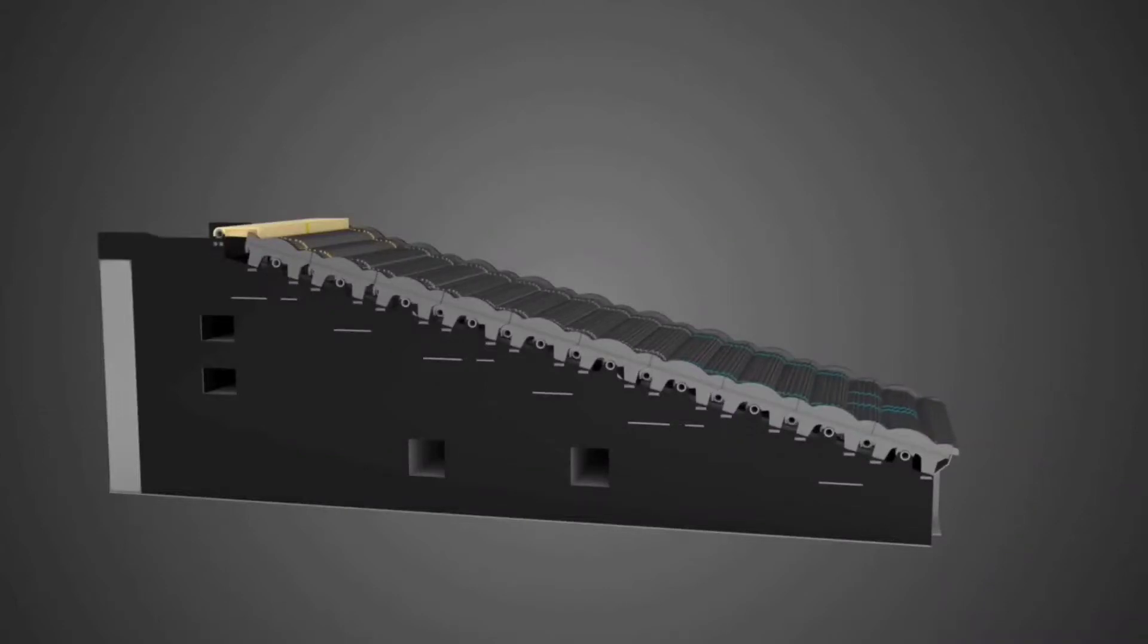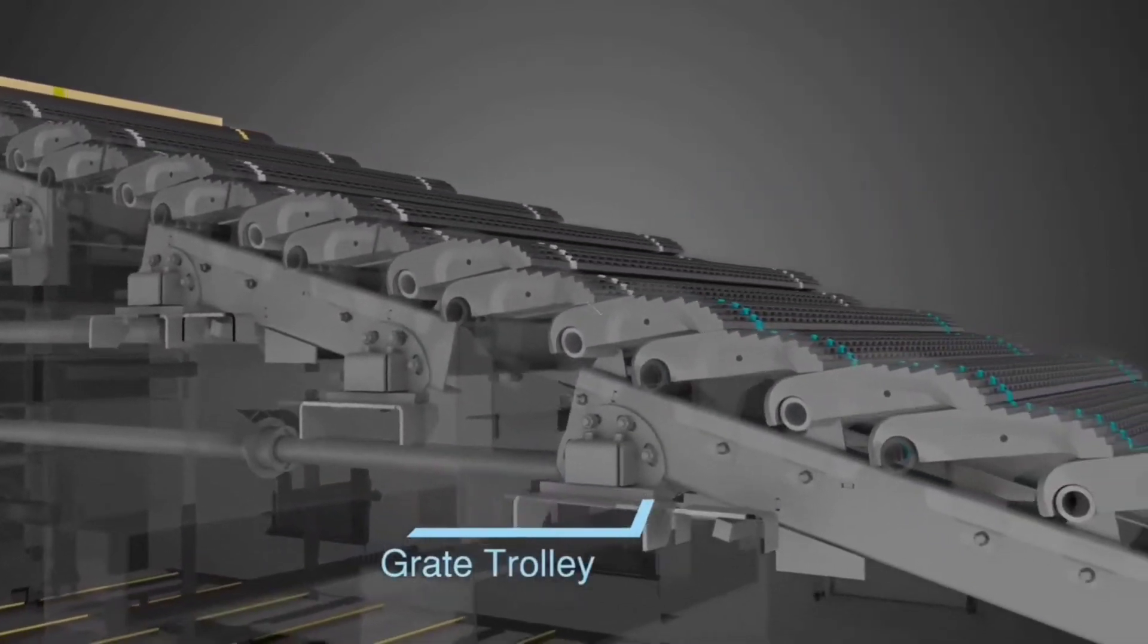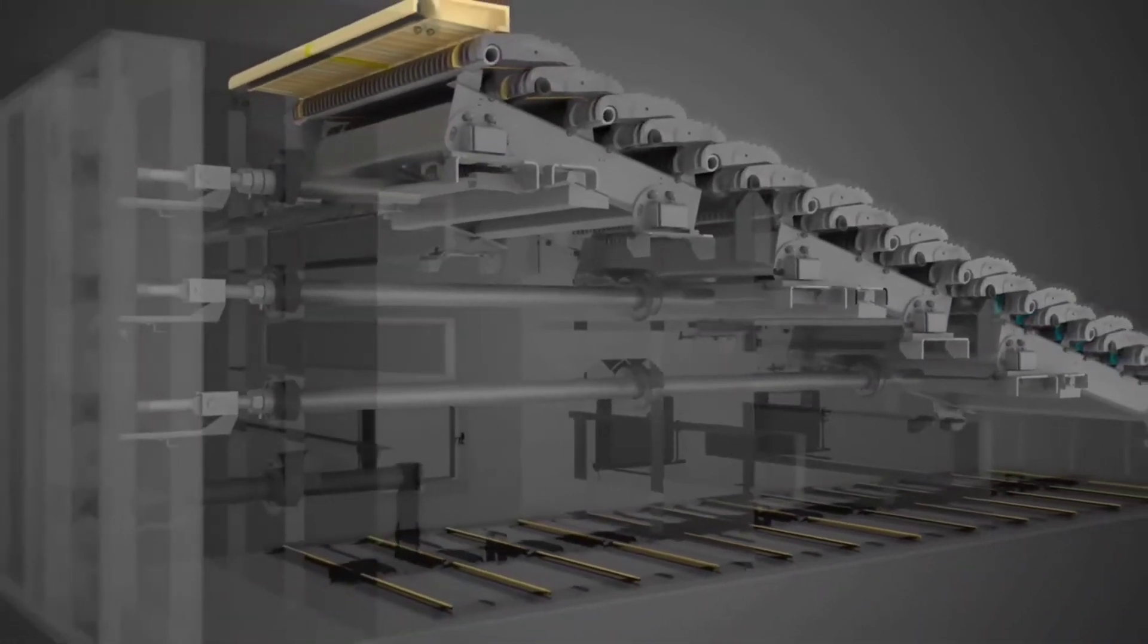As the name suggests, reciprocating grate works on the principle of reciprocating motion. It utilizes successive oscillation of grate castings mounted on different trolleys for the continuous movement of fuel. These trolleys are driven by independent hydraulic cylinders.